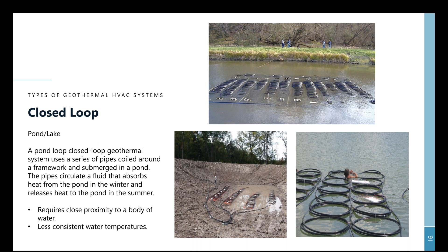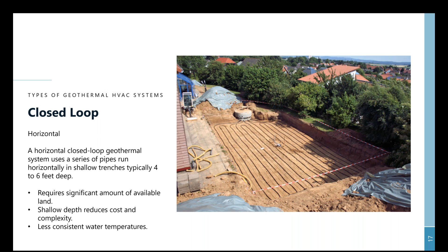Another type of closed loop system is the horizontal closed loop. Like the name implies, you are simply circuiting plastic piping in a horizontal manner in a fairly shallow trench, typically around 4 to 6 feet deep. Some of the drawbacks of the horizontal system type is that it does require a significant amount of available land. So you are going to be limited in terms of, if you have a very large capacity, you would need quite a large plot of land. The shallow depth does help reduce the cost and complexity of these types of systems because you do not have to dig quite as deep as some of the other systems we'll talk about later. But again, because it is a shallow system, you get slightly less consistent water temperatures in a horizontal arrangement.